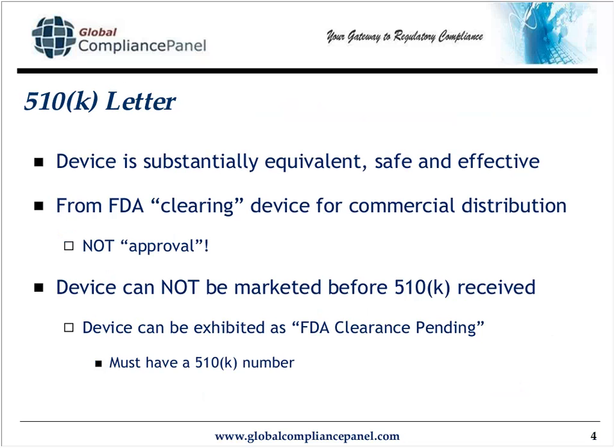I'm not usually the kind of person who likes to regulate speech, specifically inter and intra-departmental speech. However, when you hear people speaking at your company about, well, we got that 510K approval last week, what's going on? I definitely think it's incumbent upon us in the RAQA field to tenderly, to nicely, good-naturedly let people know that that's not the accurate term for a 510K, for pre-market notification. Our device is cleared for commercial distribution, and it's not approved.